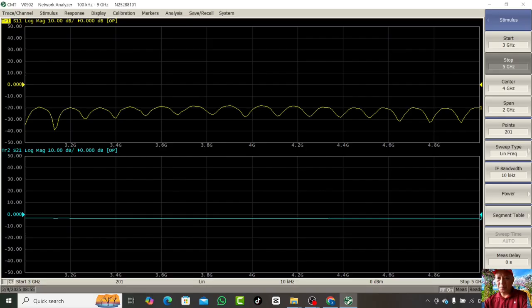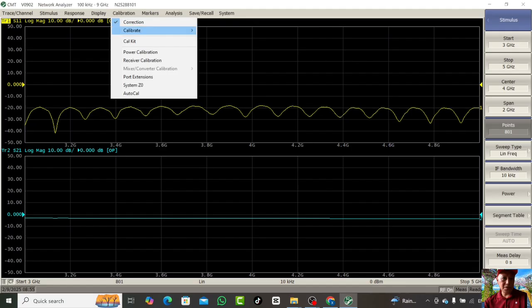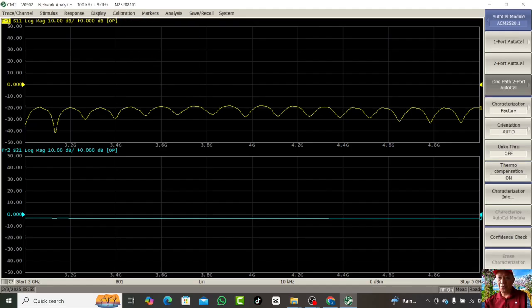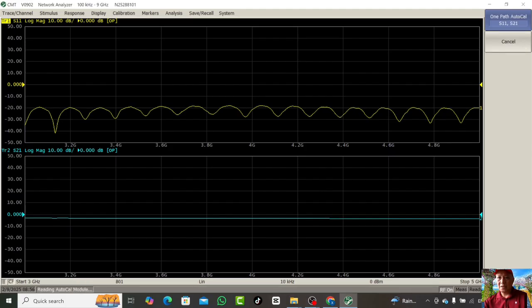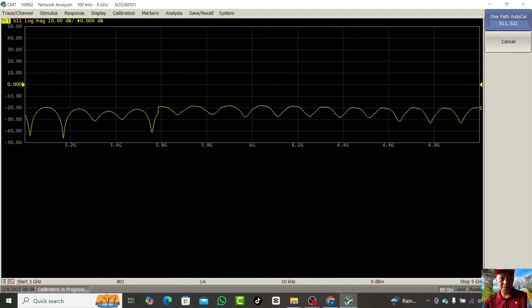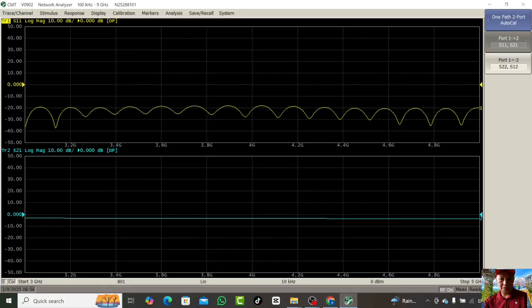And then for the points, I like to change it to a bigger number, for example 801, 1 point at the center and then 400 at both sides. We leave the IF bandwidth still at 10 kilohertz, and then we do the calibration again. Come to calibration, auto cal, one path 2-port auto cal. We still do this S11. See, it's in progress, and now the calibration is done. Let's test the filter's real frequency response after calibration.